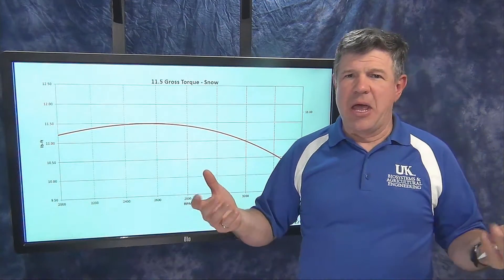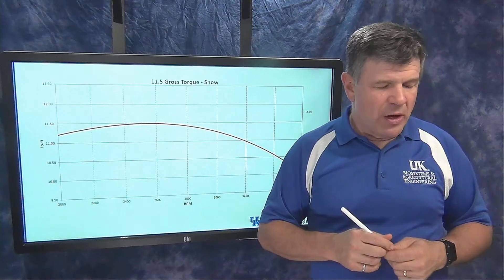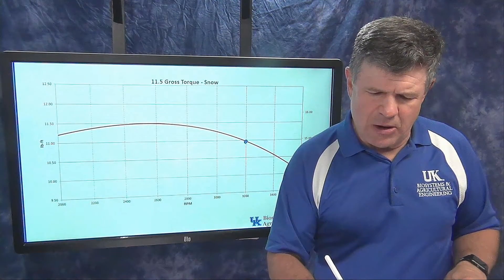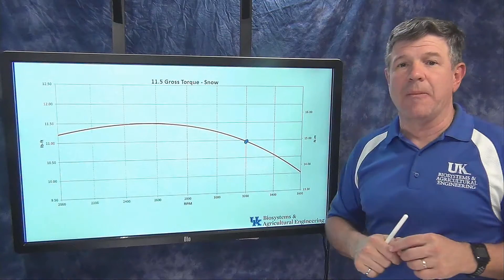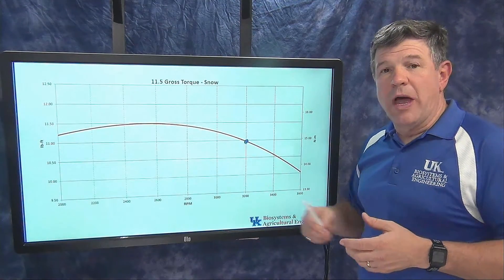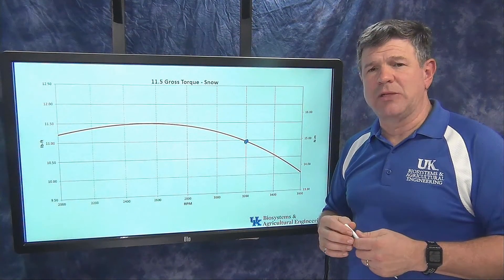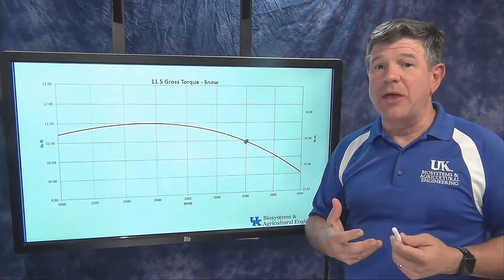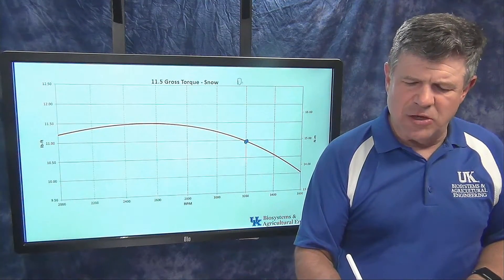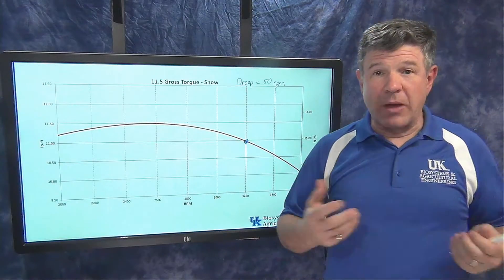If I have an application — let's say I'm building a log splitter that has to drive a hydraulic pump, and that hydraulic pump wants to run at 3,200 RPM — the pump is going to operate at that point at 3,200 RPM, where it's at maximum power. That's where I want my engine to be at maximum power when it's loaded down, when it's working hard, when I'm splitting a piece of wood. So I need to know the droop for that engine. Let's say the specifications state the droop is 50 RPM.